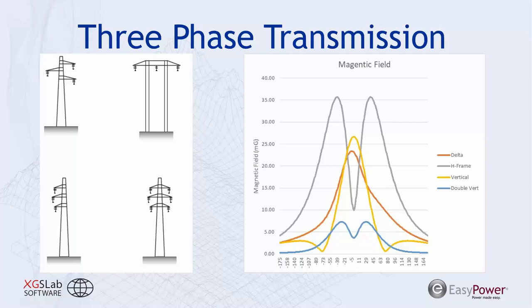Looking at the vertical configuration of the transmission line, we see this yellow line here. We have a little bit higher peak magnetic field along the center line of our transmission line, and that quickly drops off as you go farther horizontally away from that vertical compared to the delta. And then we have a double circuit vertical transmission tower in this blue.